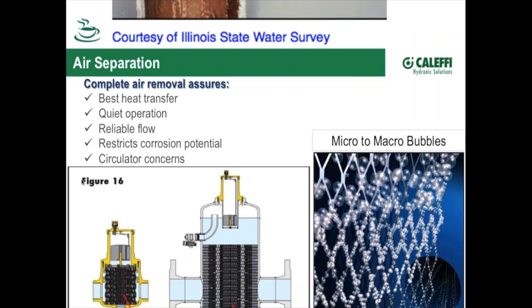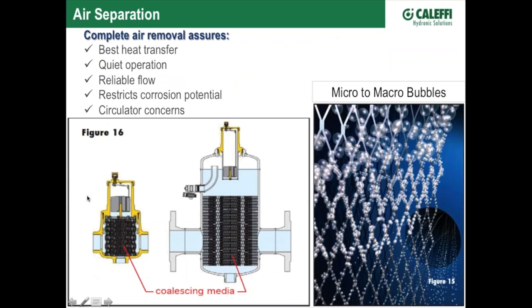All right, air separation. This is a biggie for me. For years, we had just a device that had a ramp or a scoop in it, and it would try and scoop the air out of the flow as it went through it. It did an okay job, but we need to do better than that now. We need to get little, what we call micro bubbles. In the bottom of this picture here, these are bubbles that might not even be visible to the human eye. It might appear as cloudy water when you fill a glass. That's tiny micro bubbles. It's really hard to have those just come out of an air vent without some sort of, let's say, encouragement.